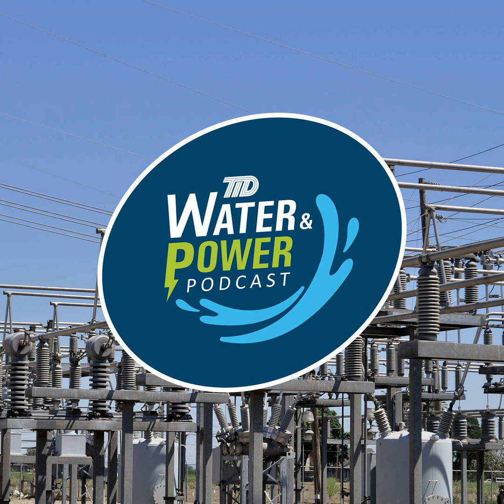That's going to vary depending on the need of the substation. If you're tying to a generating facility, you want that switchyard or substation tied in right into that generating facility. You don't want to carry more power than you need at that lower voltage - you essentially want to step right up to the system for losses, and honestly, it's just easy to locate a switchyard there at the facility.